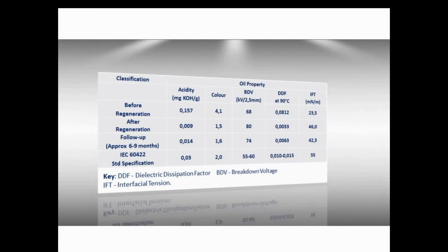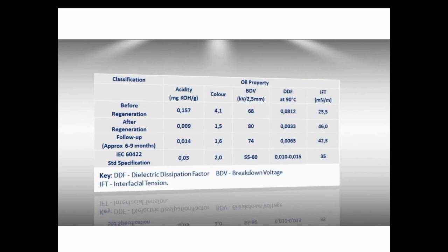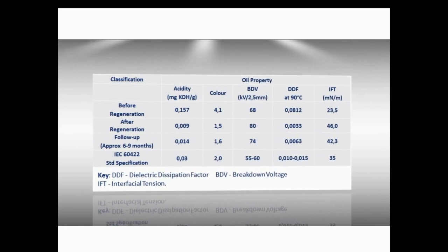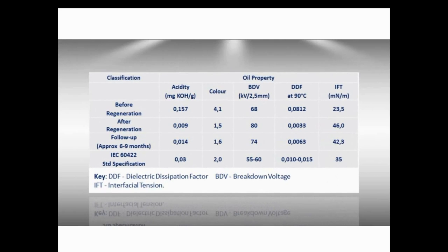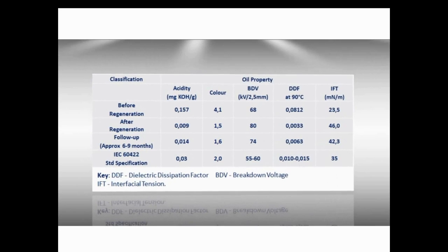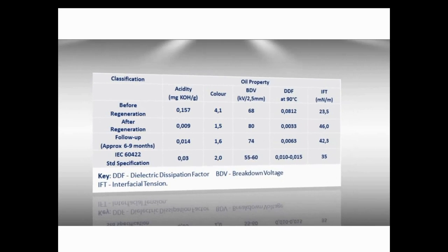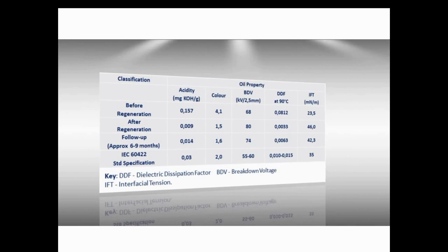Since its start, oil ages and loses its antioxidant properties. That's why we add an inhibitor, DBPC 2,6. As DBPC comes down in 2 years, we should add it again after regeneration. But even though it is different from new oil, regenerated oil will save big money.